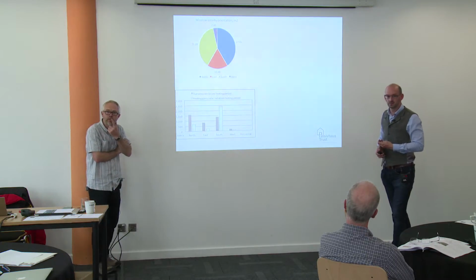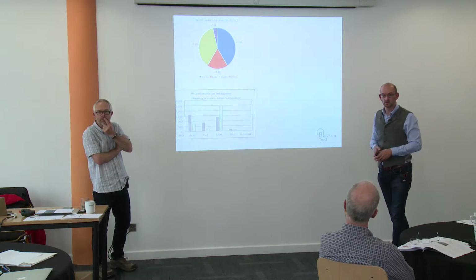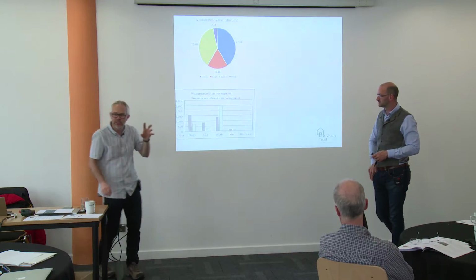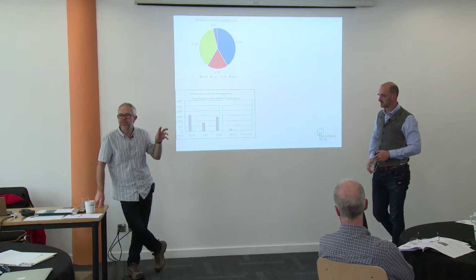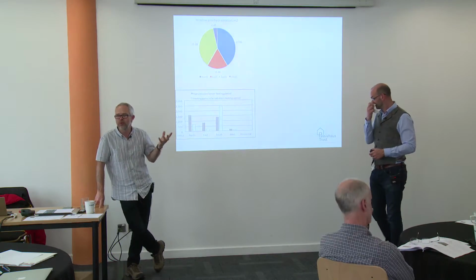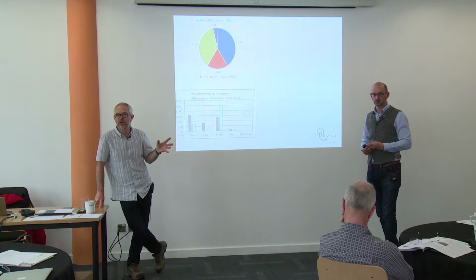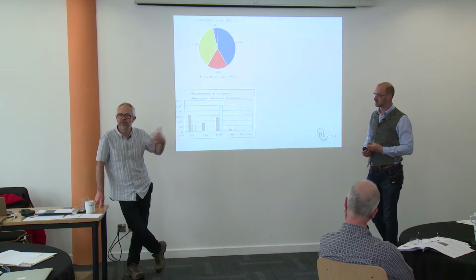I was just going to ask, the daily swing 2.5 figure, where do you find that in PHPP? It's in the summer sheet. As I say, it's two things. It's originally intended as a test that if it's beyond that, then the model, because it's a static model, not dynamic, says don't trust the daily model. The temperature swing, so that's to do with the gains really.